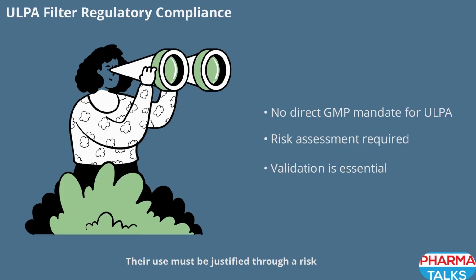Their use must be justified through a risk assessment and they must meet strict efficiency standards. If ULPA filters are chosen, they must be properly validated to ensure they deliver the required level of protection. This approach allows for flexibility, but also places responsibility on the facility to justify and document their use.